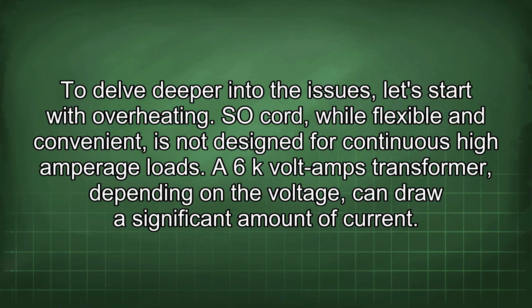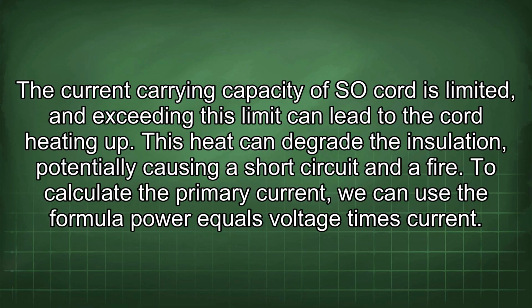SO cord, while flexible and convenient, is not designed for continuous high amperage loads. A 6 kVA transformer, depending on the voltage, can draw a significant amount of current. The current carrying capacity of SO cord is limited, and exceeding this limit can lead to the cord heating up. This heat can degrade the insulation, potentially causing a short circuit and a fire.